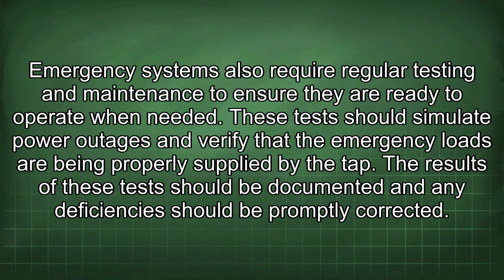Emergency systems also require regular testing and maintenance to ensure they are ready to operate when needed. These tests should simulate power outages and verify that the emergency loads are being properly supplied by the tap. The results of these tests should be documented and any deficiencies should be promptly corrected.